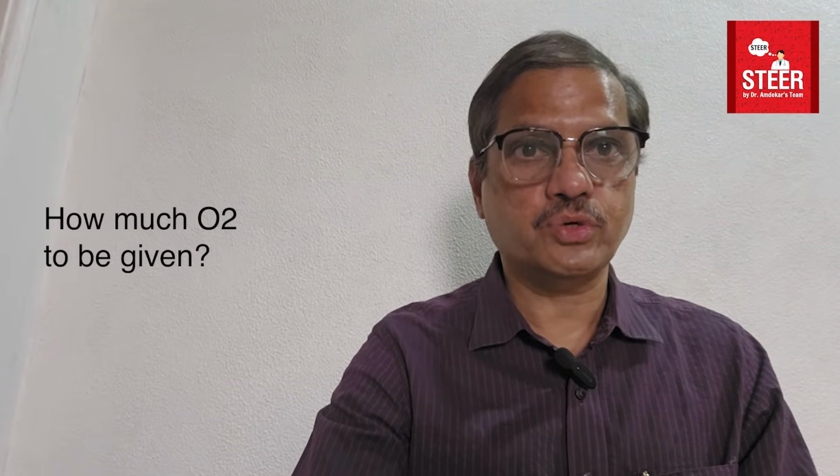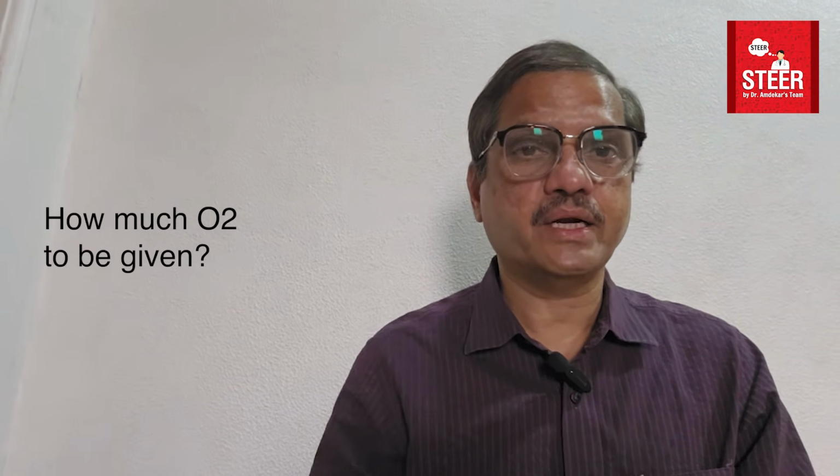Oxygen is sourced in the hospital through the central oxygen system, or sometimes through oxygen cylinders of small or large size, something like 1350 liters to 6500 liters, and sometimes even oxygen concentrators. When there is a home oxygen requirement, many times we use commercially available oxygen concentrators which can deliver as much as 5 liters per minute. So depending upon the source, delivery and requirement, the delivery system or source can be defined.